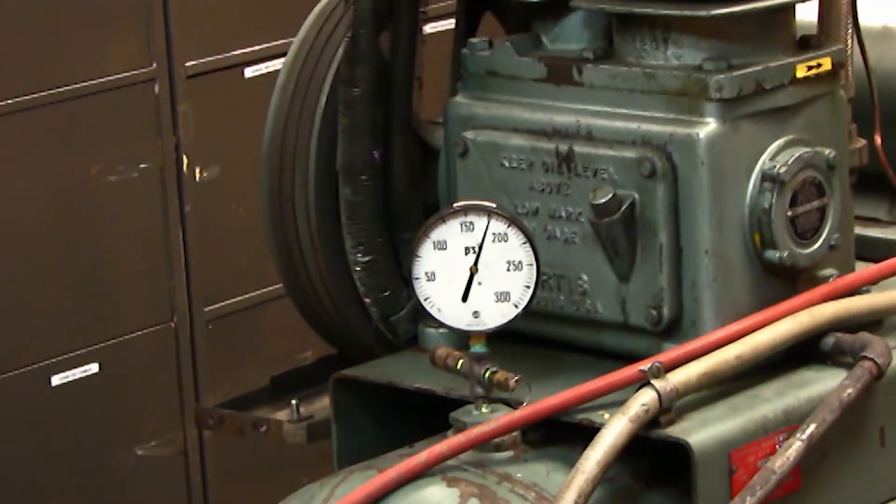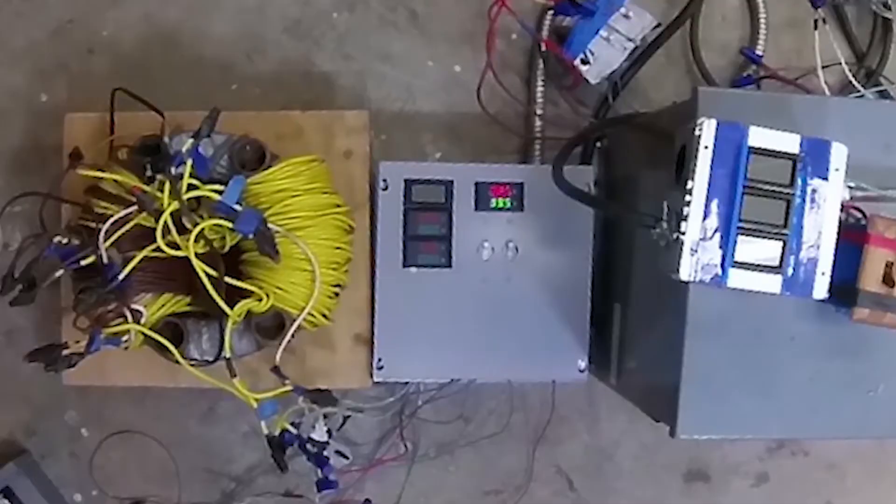So that's what you need in this situation. You need the starting power of the transformer converter, yet you need to raise the voltage up to 460. And this is a very simple way to do it because the capacitors and everything you're doing is a 240-volt system. You're not messing around with the high-voltage capacitors.